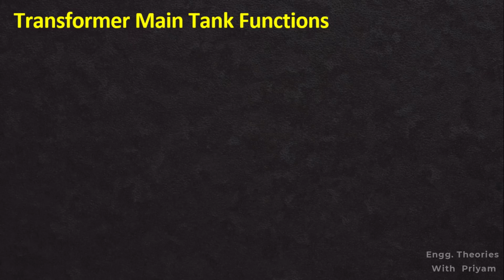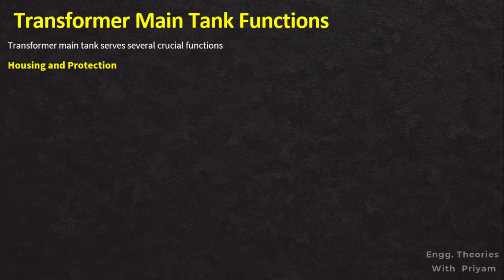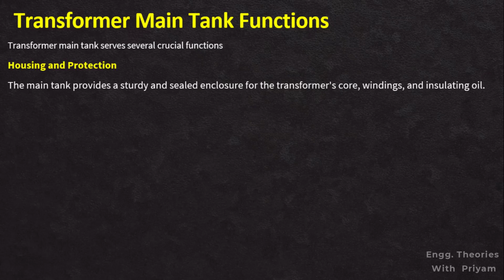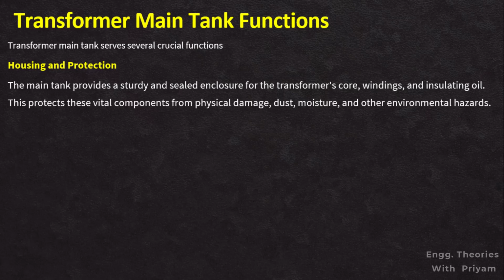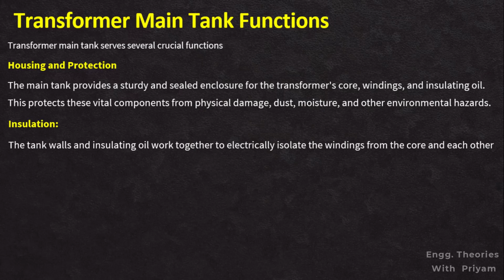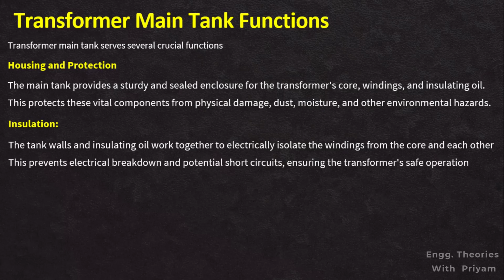The transformer main tank serves several crucial functions, ensuring the safe and efficient operation of the transformer. First is housing and protection. The transformer main tank provides a sturdy and sealed enclosure for the transformer core, windings, and insulating oil. This protects these vital components from physical damage, dust, moisture, and other environmental hazards. Insulation. The transformer's tank walls and insulating oil work together to electrically isolate the windings from the core and each other, and this prevents electrical breakdown and potential short circuit, ensuring the transformer's safe operation.